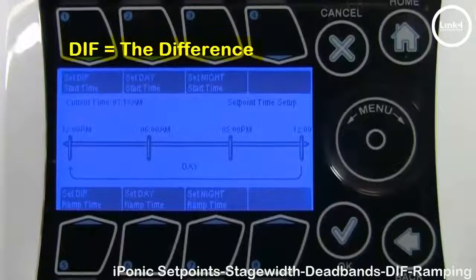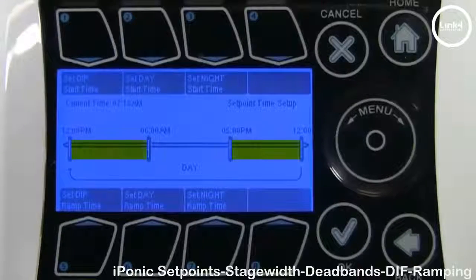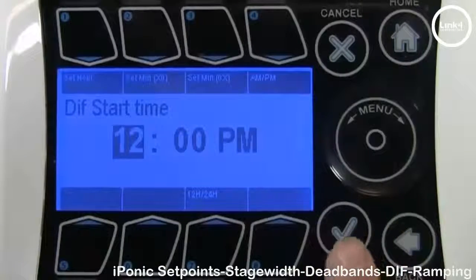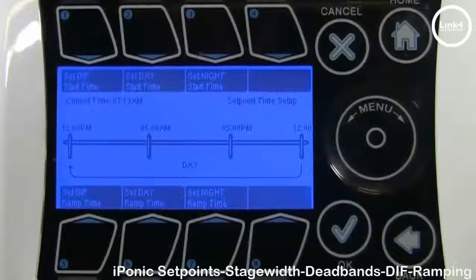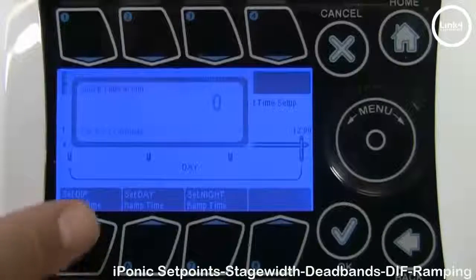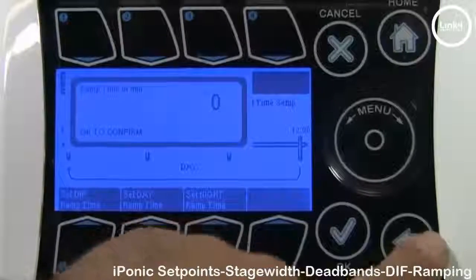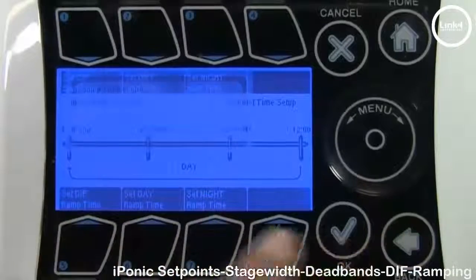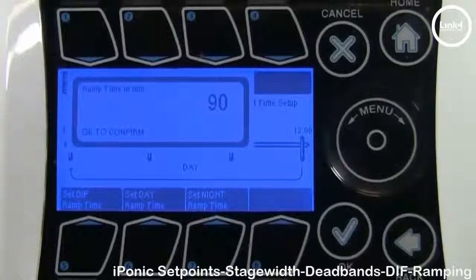Button number 1 sets the DIF time, which is the difference between day and night set point times. You can put it within the daytime period or within the nighttime period — you decide. We're going to set the DIF start time at 12 p.m. At the bottom you have number 5 set DIF ramp, number 6 set day ramp, and number 7 set night ramp. If you hit button number 5, a value of zero indicates immediate temp change between times, 30 means a 30-minute transition between temp set points, and 90 — the max ramp time — equals a one and a half hour transition between temp set points.